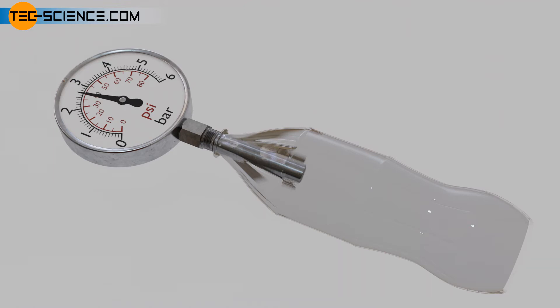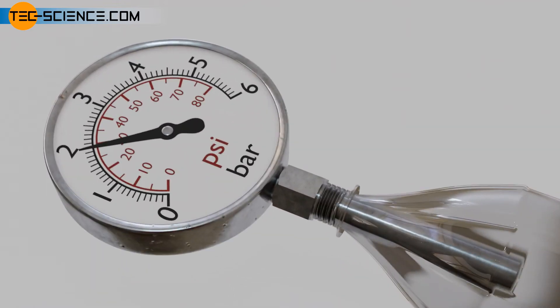The higher the temperature of the liquid, the stronger it tries to expand and the stronger the pressure increase will be at a constant volume. This principle can therefore be used to determine the temperature from the pressure rise on a calibrated scale.